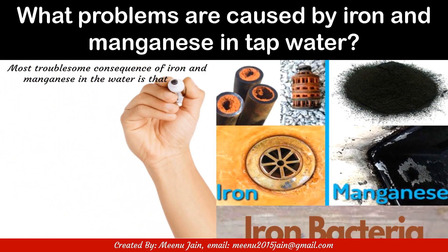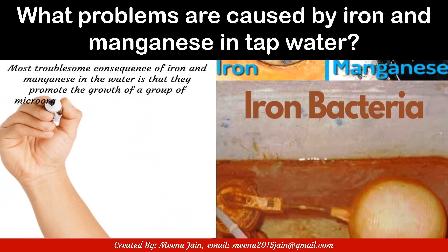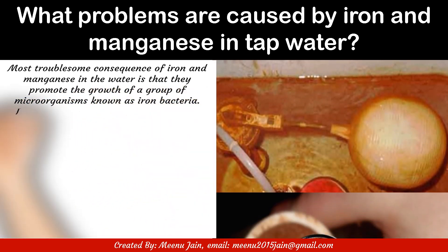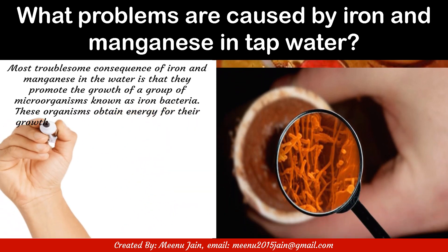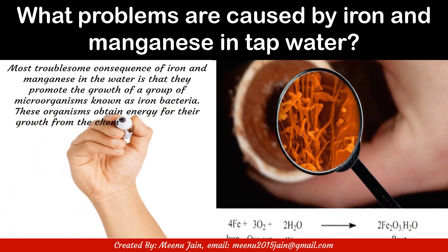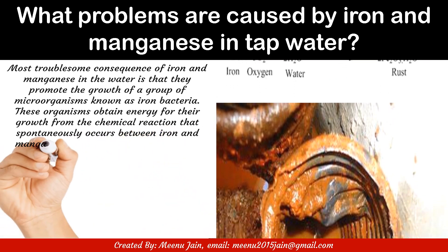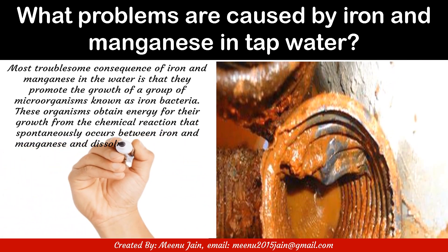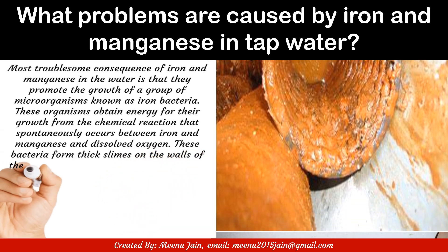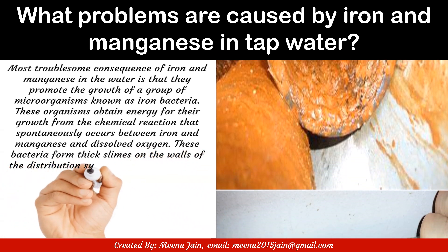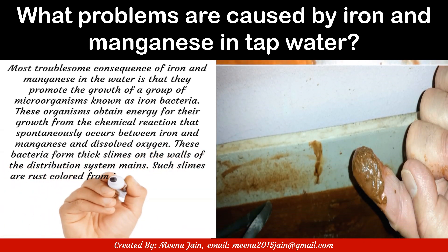The most troublesome consequence of iron and manganese in water is that they promote the growth of a group of microorganisms known as iron bacteria. These organisms obtain energy for their growth from the chemical reaction that spontaneously occurs between iron and manganese and dissolved oxygen.